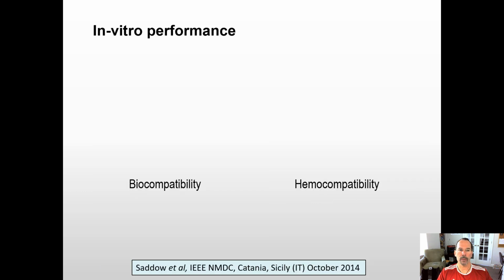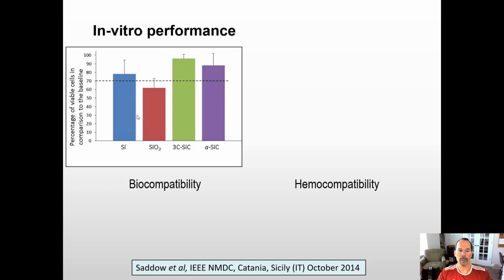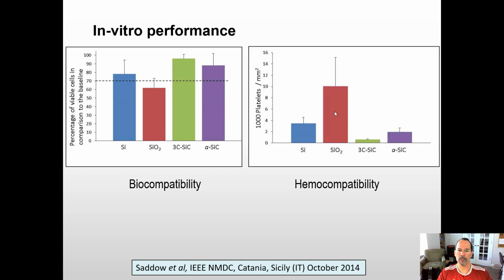Okay. So what about the in vitro performance? We looked at biocompatibility using ISO 10993, and we see that silicon passes the test over 72 hours, or maybe it was 48 hours, but eventually over a longer time, silicon fails the ISO standard. Oxide fails right from the get-go. Cubic silicon carbide and amorphous do quite well. Looking at hemocompatibility, where we're looking at platelet attachment and activation on the surface, we see again that oxide is just not a good material to be in contact with the blood. Cubic silicon carbide is excellent, and amorphous is quite good as well.